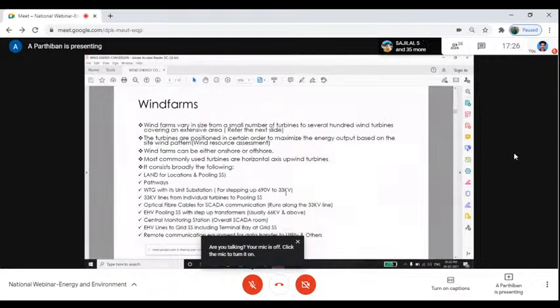What is a wind farm? We can say it is a group of wind turbines joined in a pooling substation, which is further connected to a grid substation. I will explain what all these terminologies are. Each individual wind turbine will have a capacity of 2 megawatt, 3 megawatt, like that. So, for example, a 300 megawatt wind farm with 3 megawatt turbines means 100 WTGs.